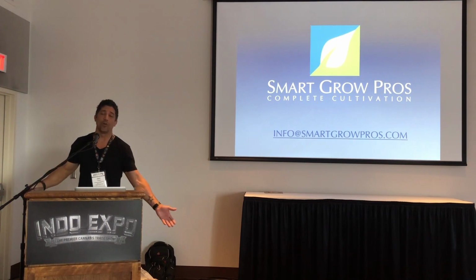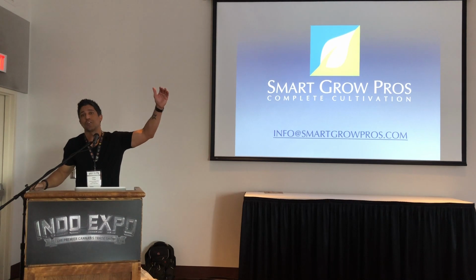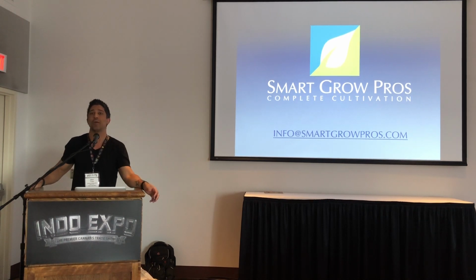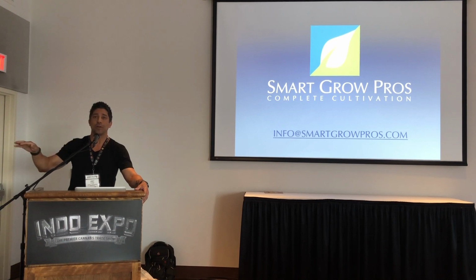So then you have this lower level of humidity that you have to deal with. The higher level is going to have less because the light load and heat load is higher up there and it's going to burn off a bit more of that humidity. And the bigger problem really comes in the off hours, when the lights turn off. Because when the cooling shuts down, it hits its target number. Say you go from 82 degrees, you come down to 62. When the HVAC shuts off, the dehumidification that the HVAC was supporting and the lights were helping with is gone.